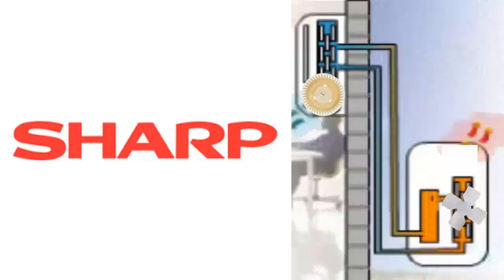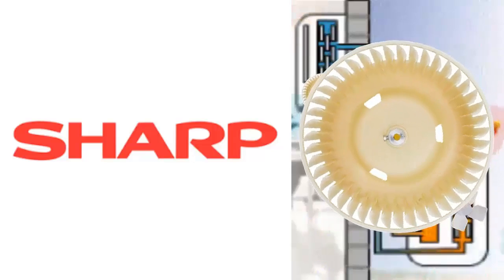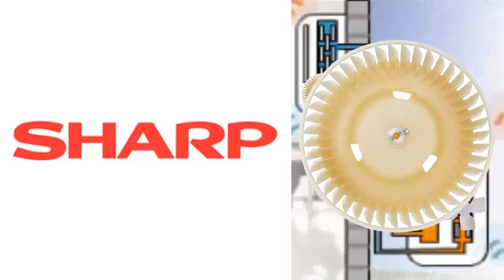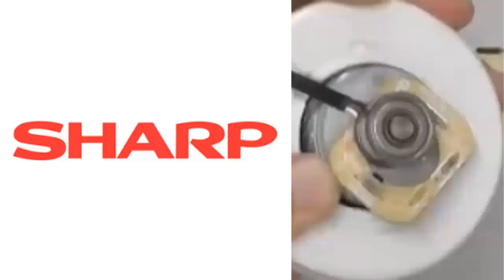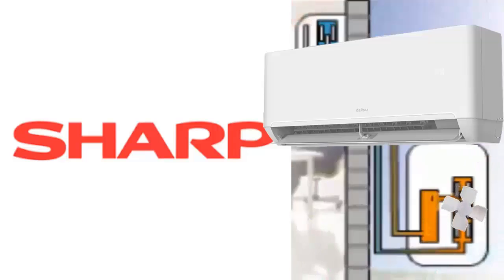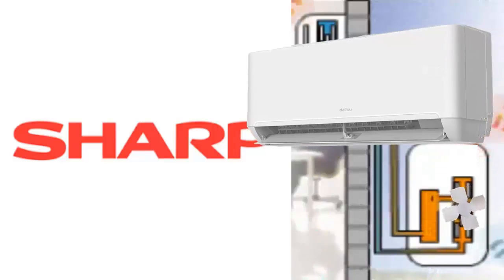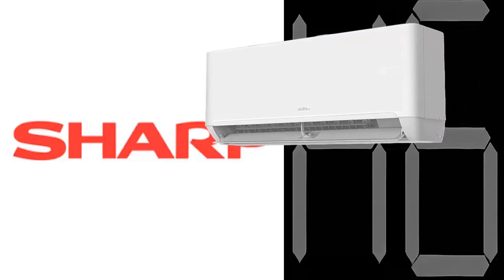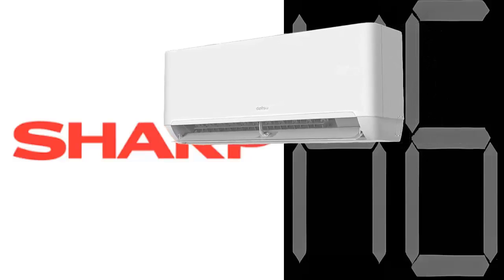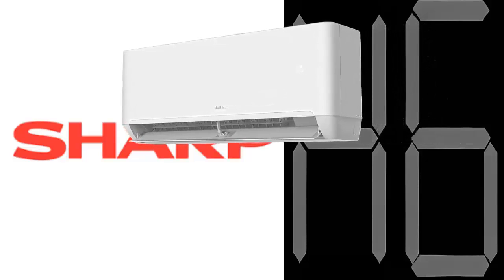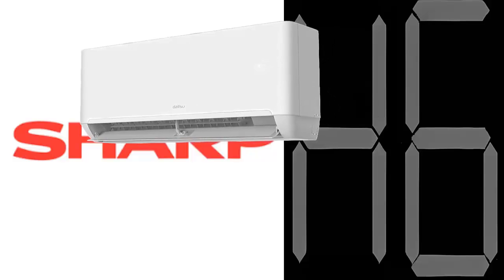Problems with the fans of Sharp air conditioning units are generally identified through the fan motor speed sensor, known as the Hall effect sensor. When the problem occurs with the indoor unit fan, the error code H6 is usually generated for BLDC type fans. These fans can be identified as they are powered directly by 5 wires.